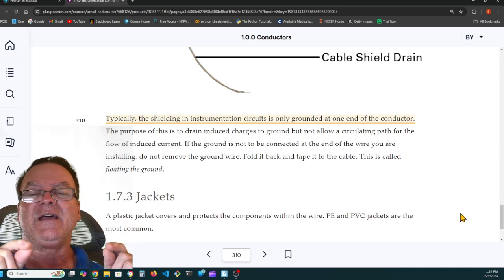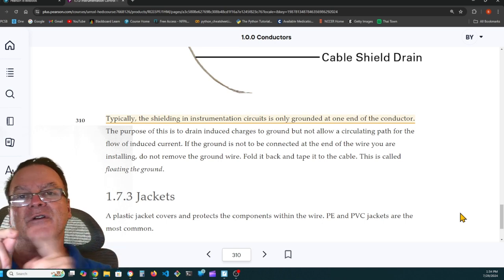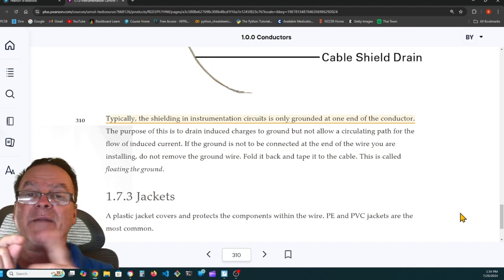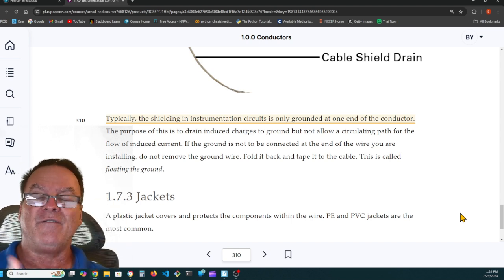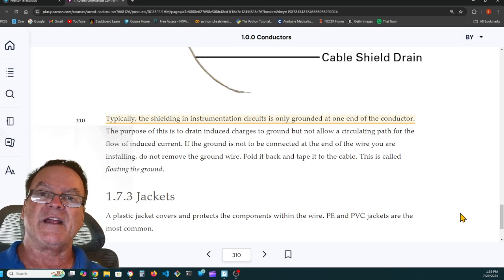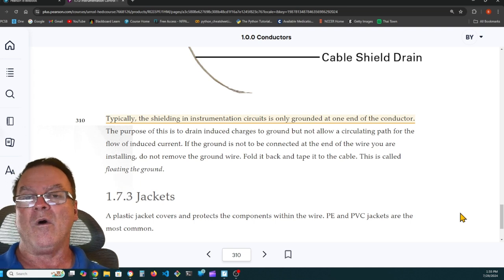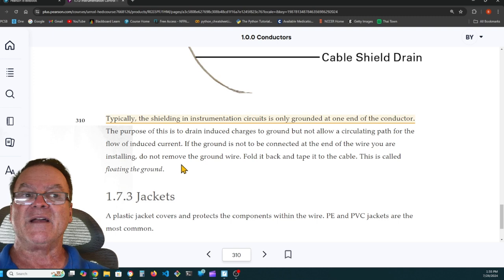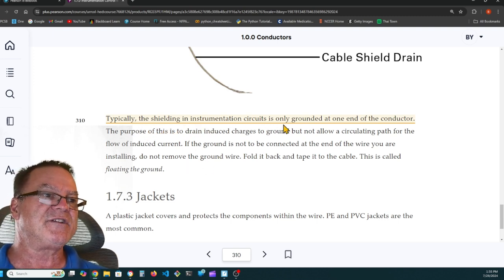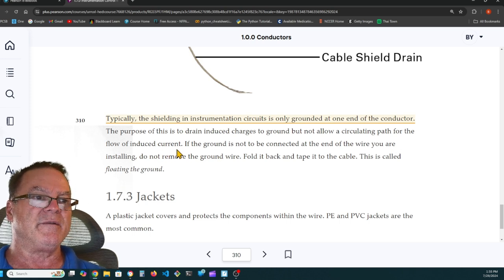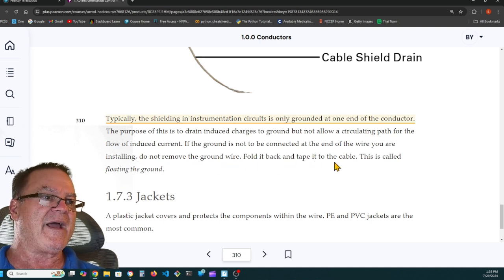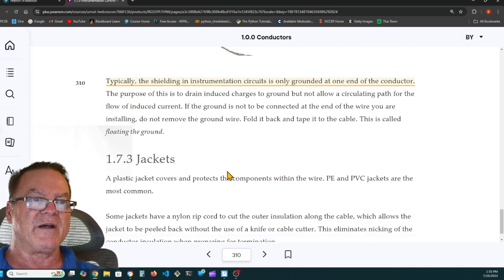If we were to ground it at both ends, then you would have fault currents or induced voltages or currents running in both directions, and it would again simulate a false message. So that's why they only ground it at one end, so that all the stray currents go toward that one point and they don't get mistaken for a message. This is a highlight. It says typically the shielding in instrumentation circuits is only grounded at one end of the conductor. The purpose of this is to drain induced charges to ground, but not allow a circulating path for the flow of induced current. If the ground is not to be connected at the end of the wire you are installing, do not remove the ground wire. Fold it back and tape it to the cable. This is called floating the ground.